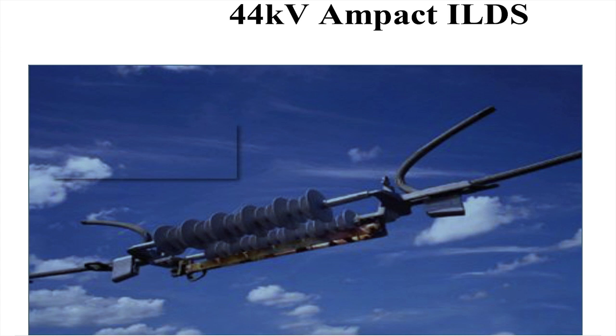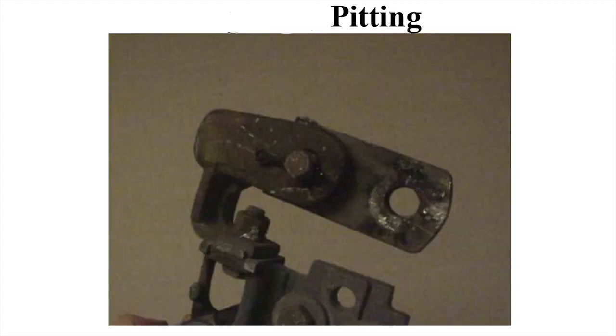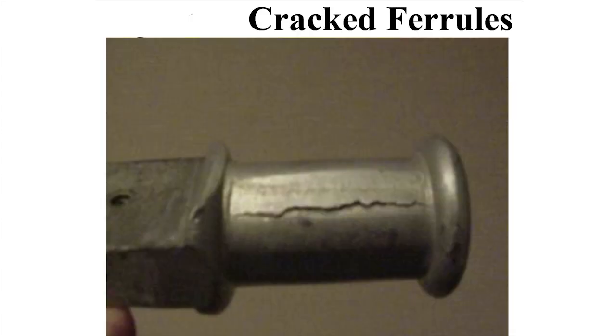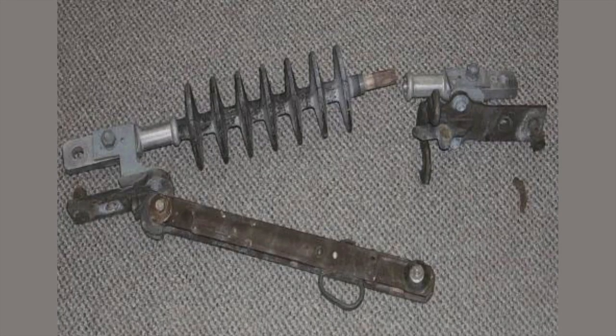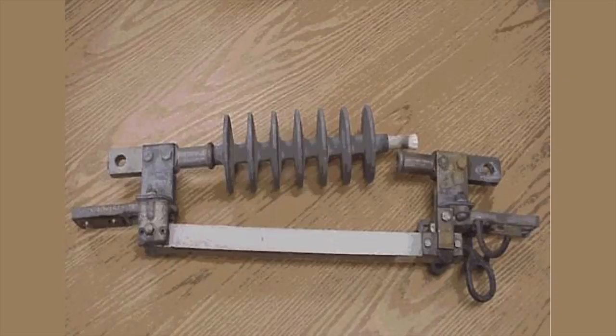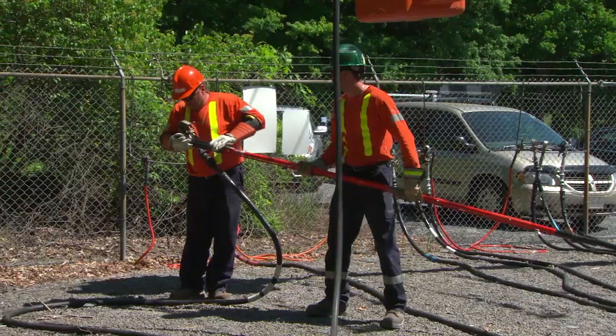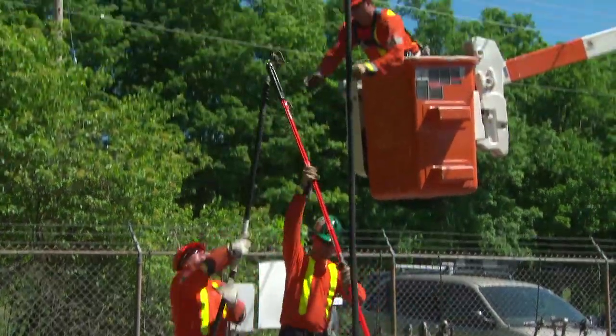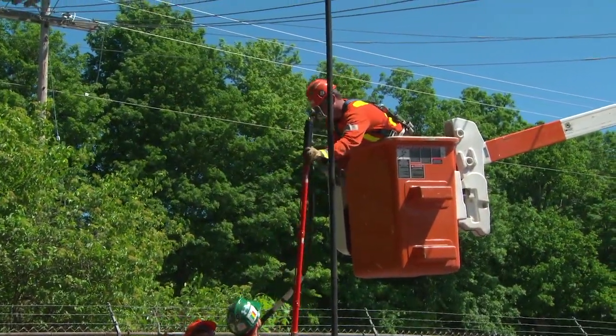If this is not possible, you must inspect switches from an aerial device for pitting, cracked ferrules, signs of arcing, or pin discoloration. If no abnormalities are found, isolate the feeders to hang the cables. The preferred isolating device is an MSO.